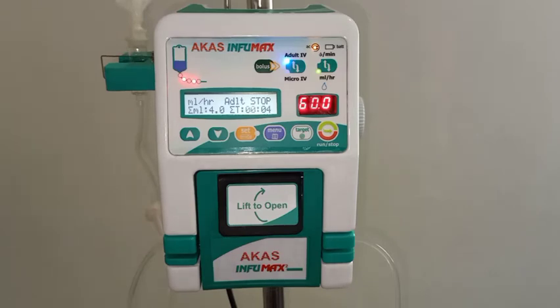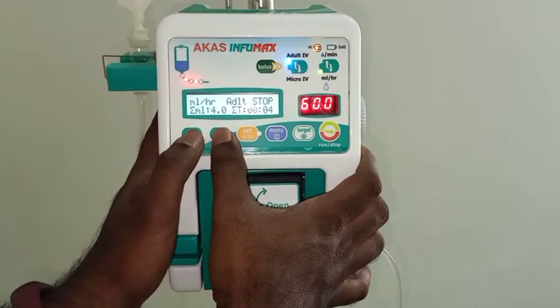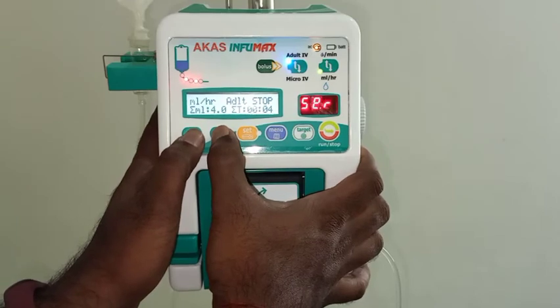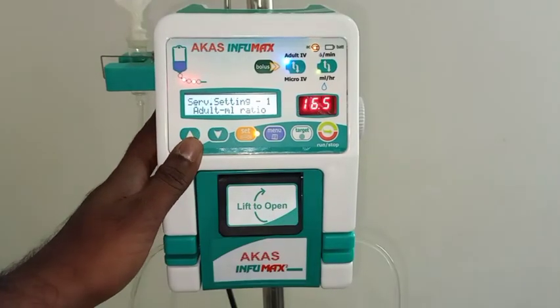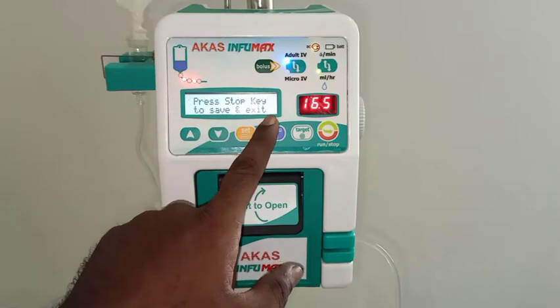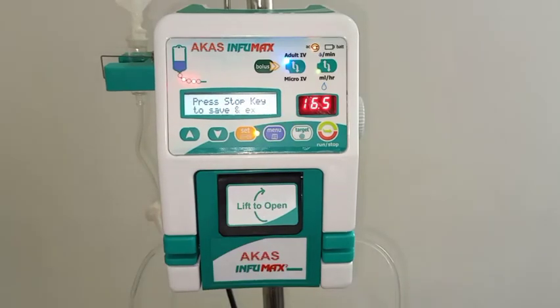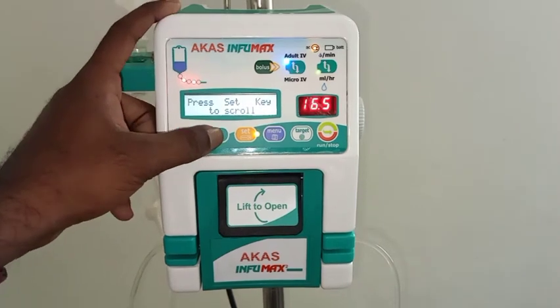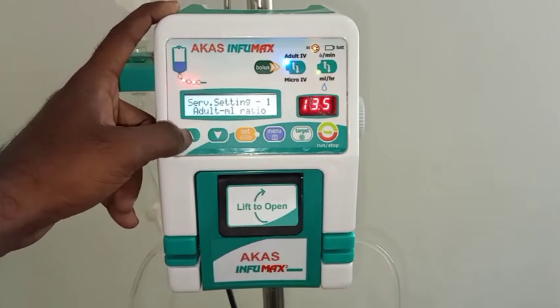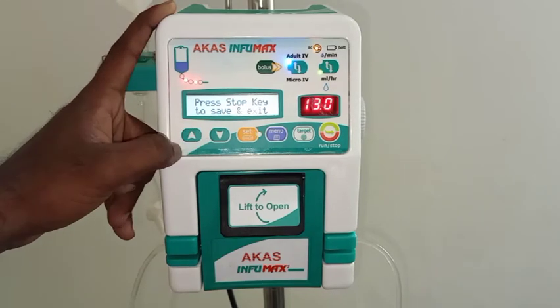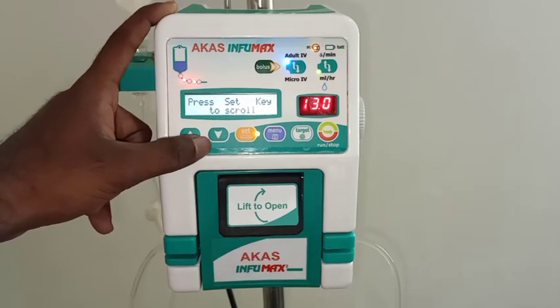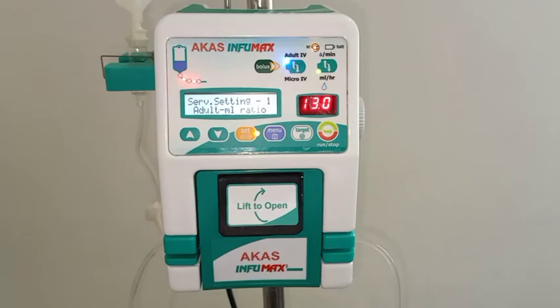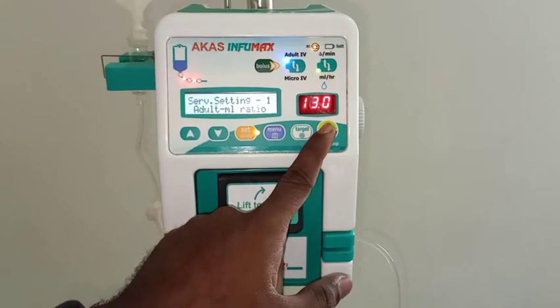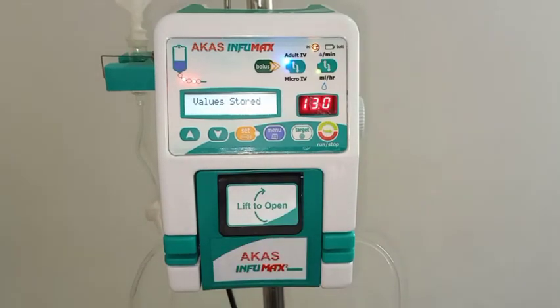Now we have to go into service settings by long pressing the increment and decrement key at a time. Service setting. See, here it's asking adult ml ratio. We have got the ratio of 13.2. So we have to keep the ratio here. 13.0. As a round off, we can keep the value as 13.0. And press the run stop key to save the value stored.